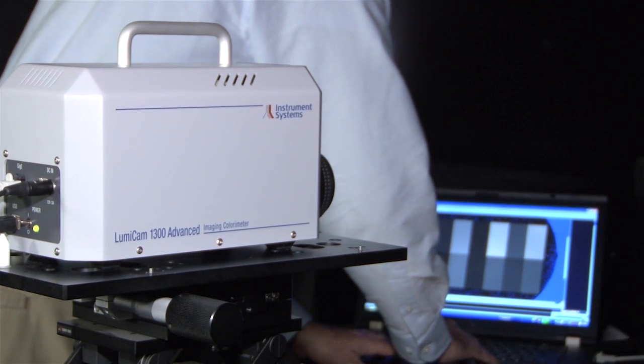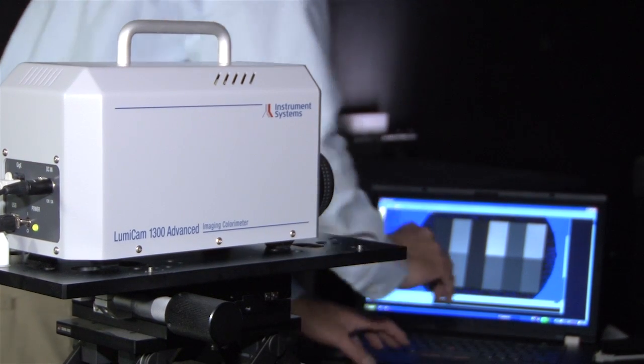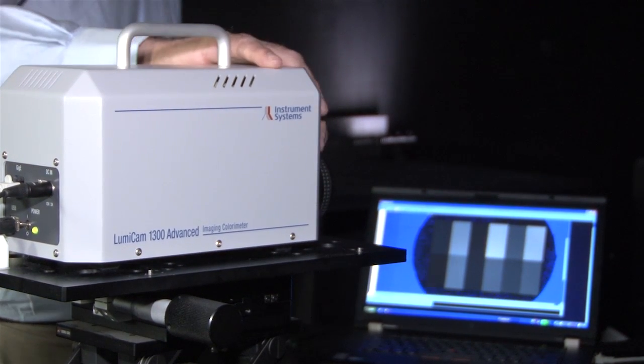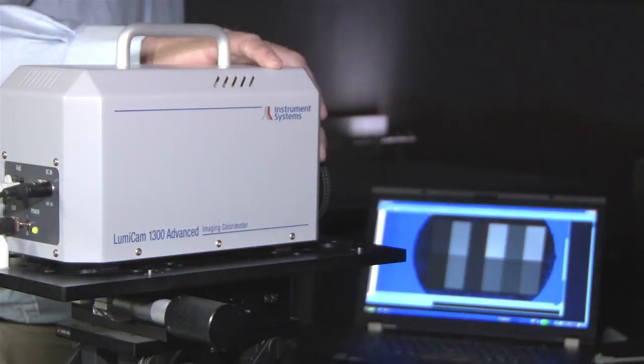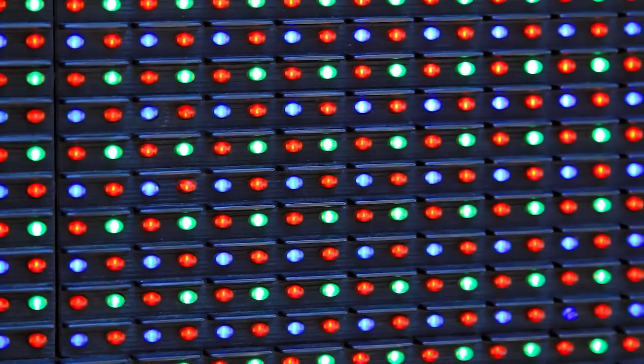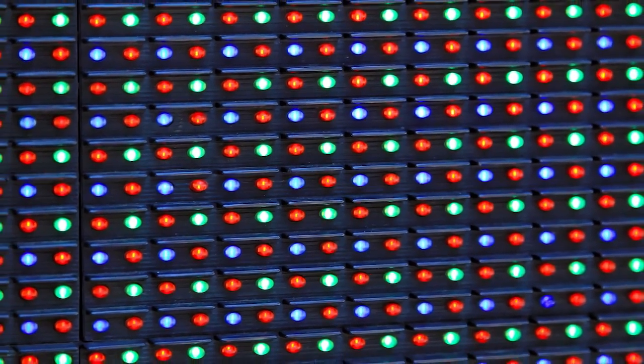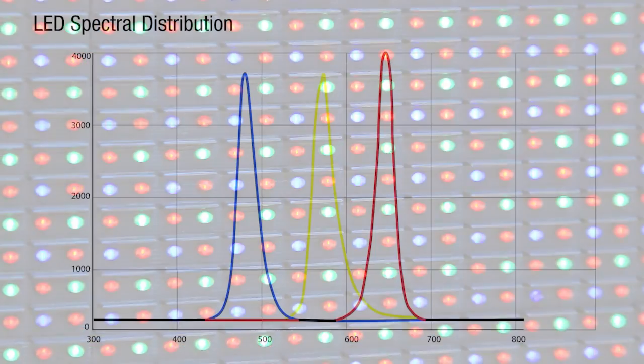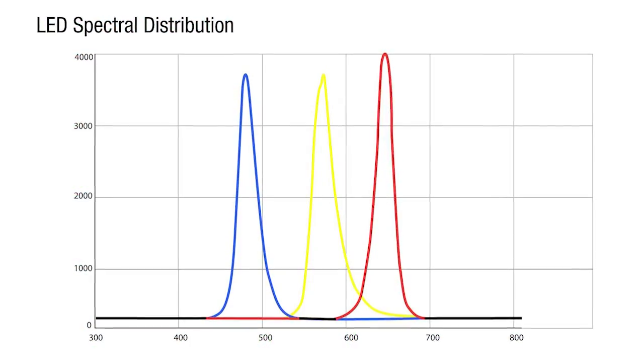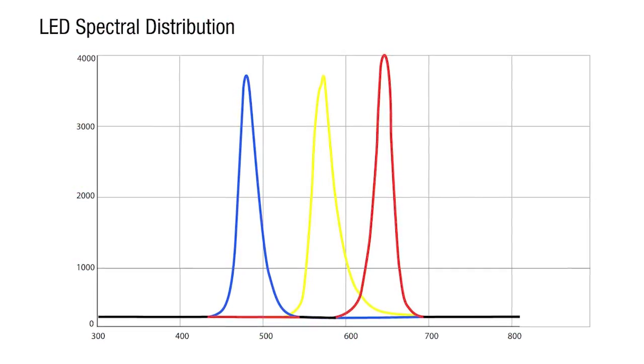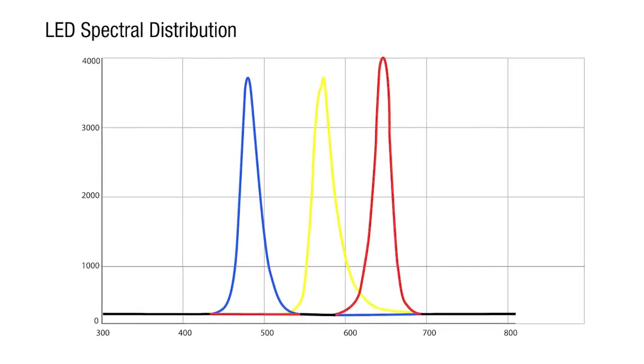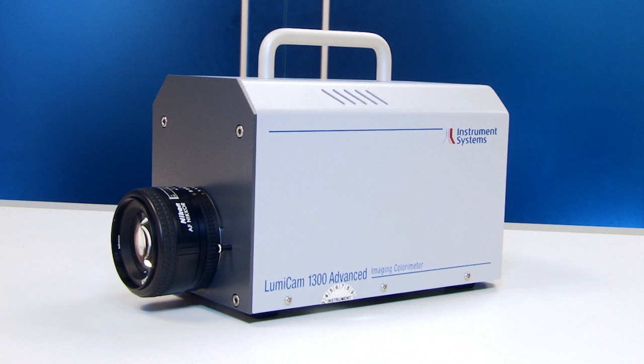The new LumiCam 1300 Advanced has increased color accuracy and can precisely measure today's LED products despite their narrow band spectral distribution. This specification has been a challenge for imaging light measurement devices until now.